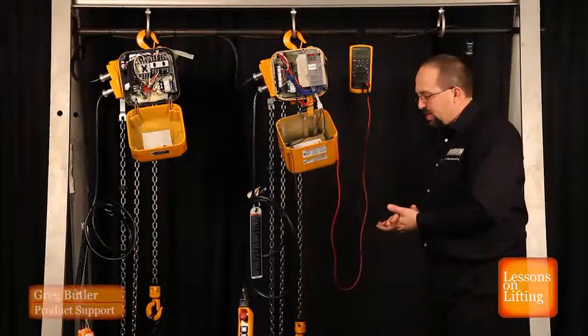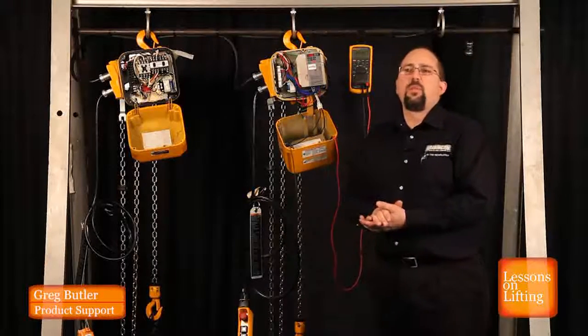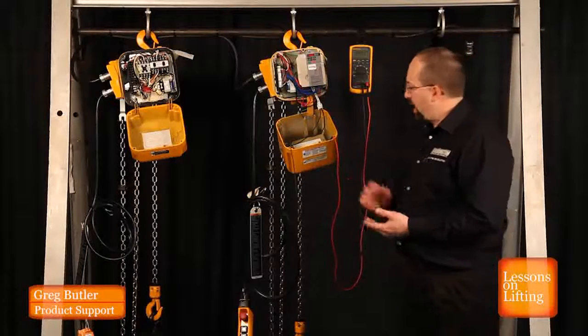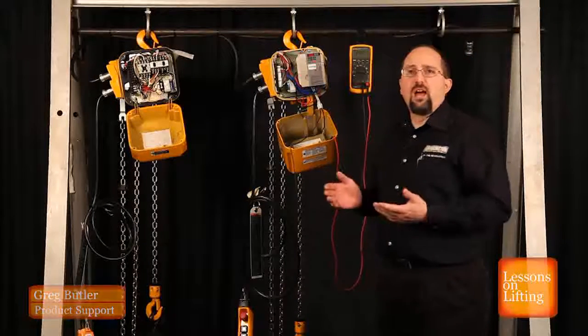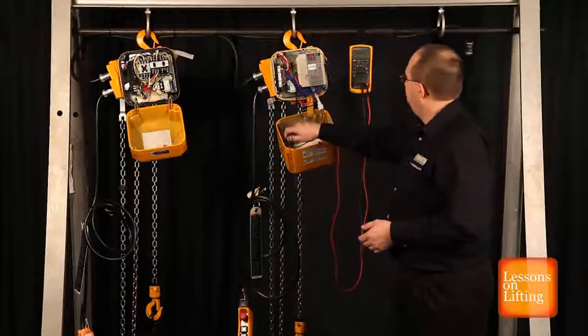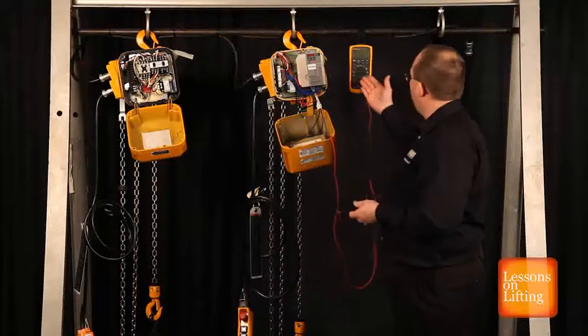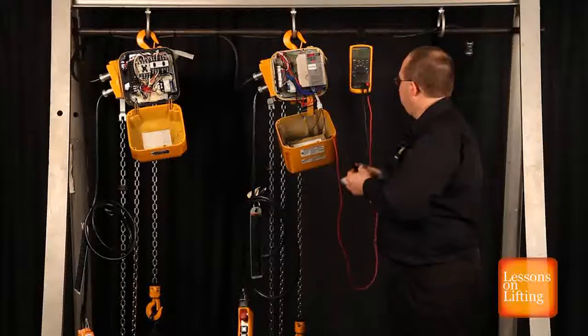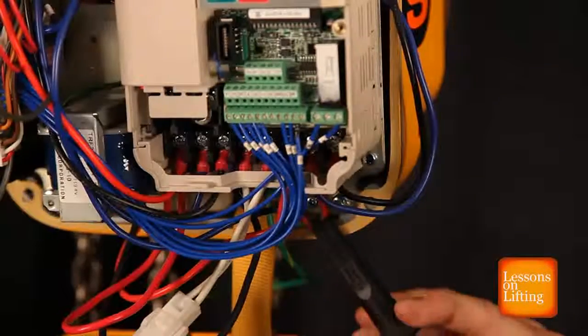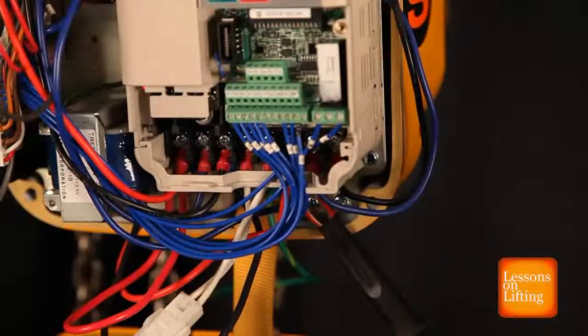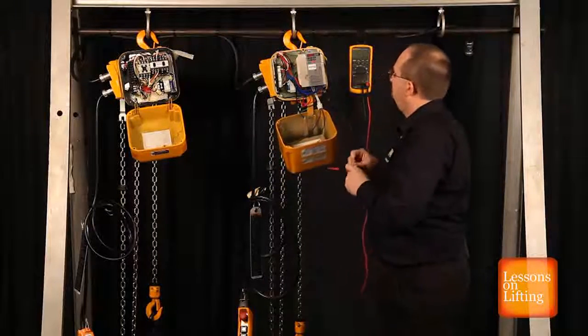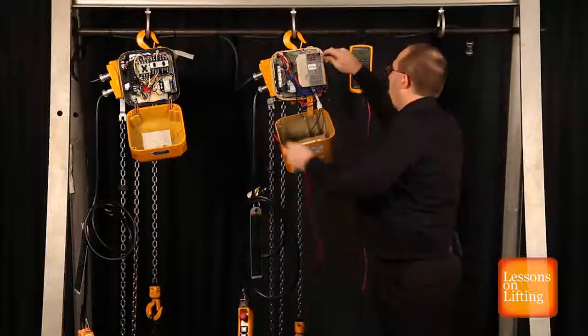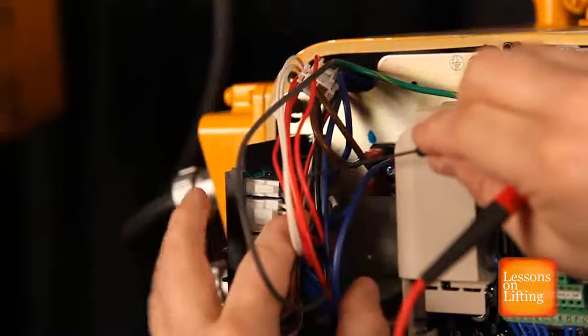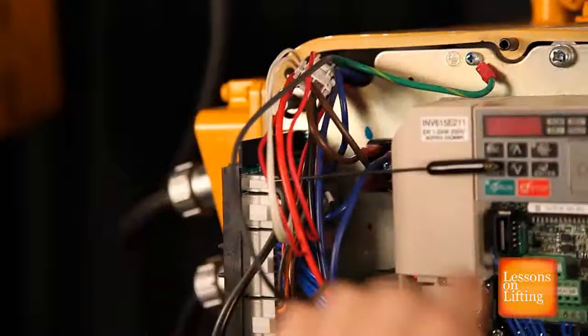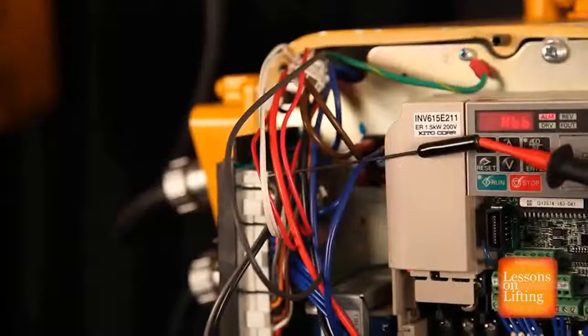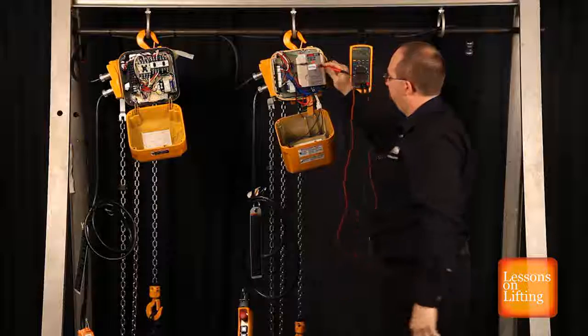Okay, so since our e-stop button was released, we know we must have some other type of problem. To begin troubleshooting, we're going to check and make sure we have control voltage coming out of the transformer. To do that, we will make sure, number one, that our meter is set to read AC voltage. We'll connect to a good ground, and we're going to check and make sure that we have control voltage on CN13 on the black wire. Right there we have 124.8 volts.